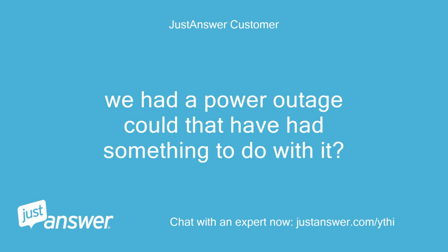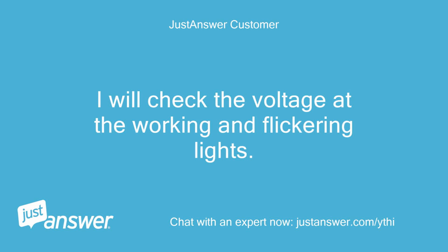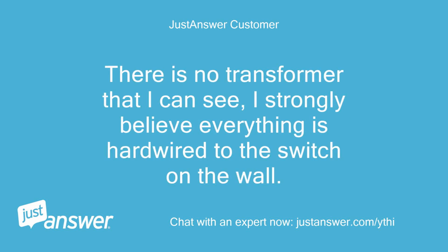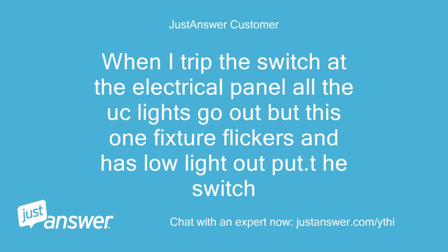We had a power outage. Could that have had something to do with it? I will check the voltage at the working and flickering lights. There is no transformer that I can see. I strongly believe everything is hardwired to the switch on the wall. When I trip the switch at the electrical panel, all the UC lights go out, but this one fixture flickers and has low light output.